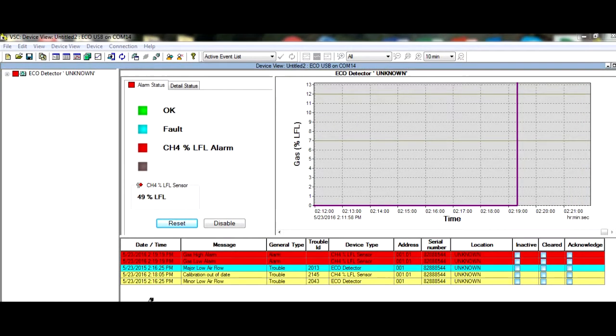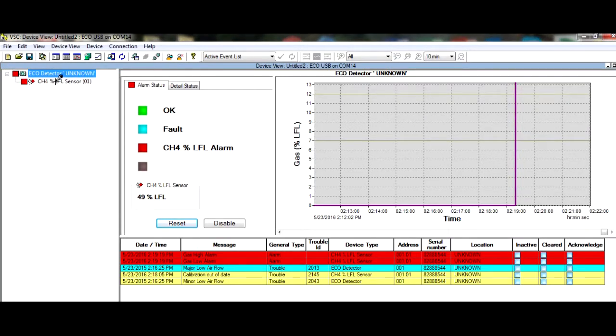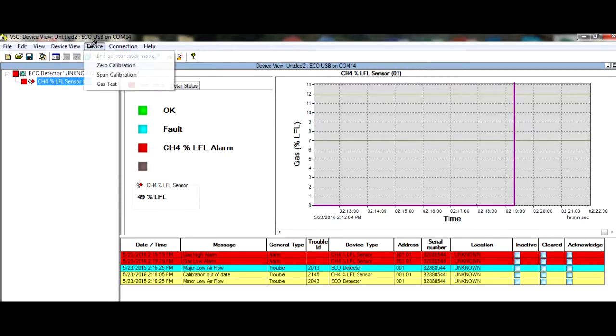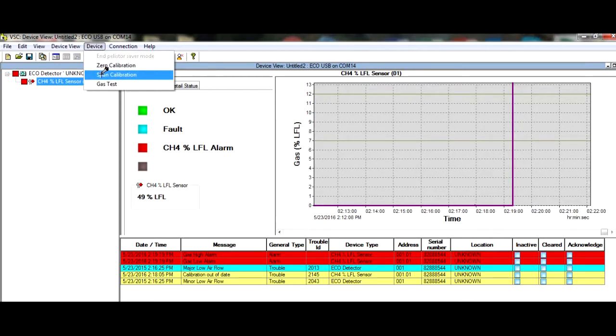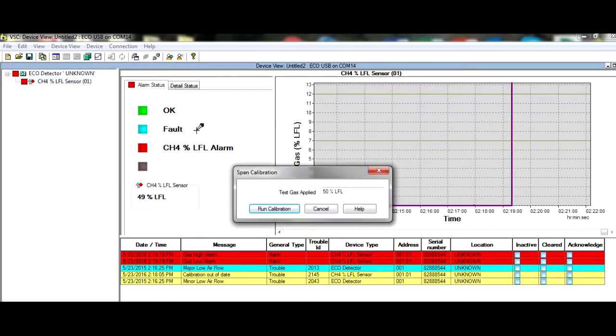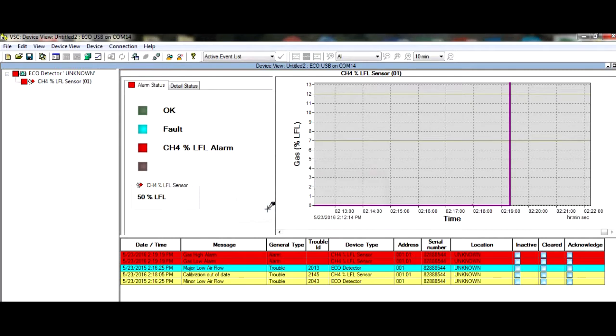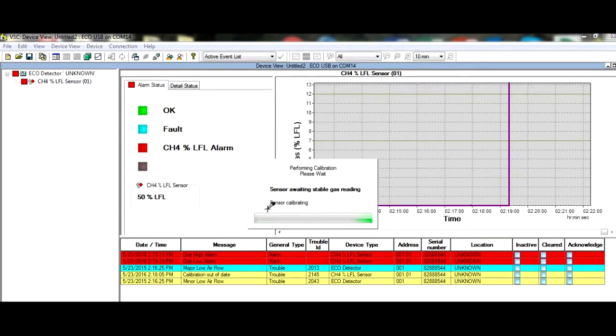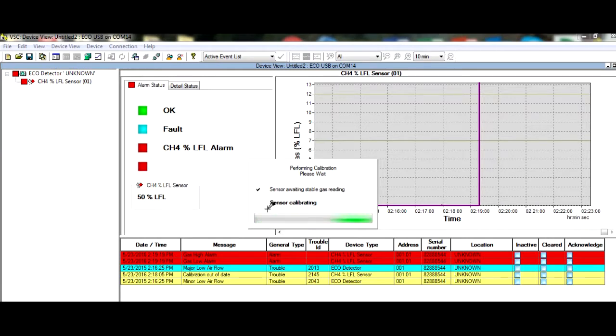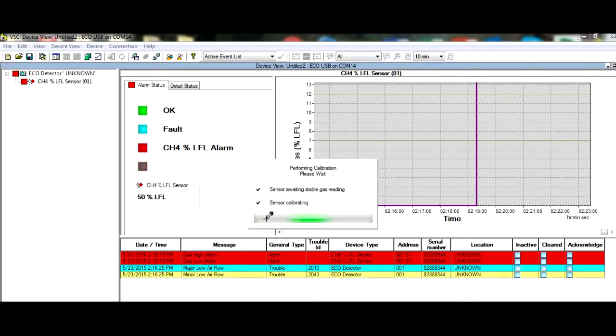Now that the gas reading has stabilized, we can span calibrate the detector. Highlight the sensor. Go to Device, go to Span Calibration, confirm the calibration concentration, run the calibration. The calibration is now complete.